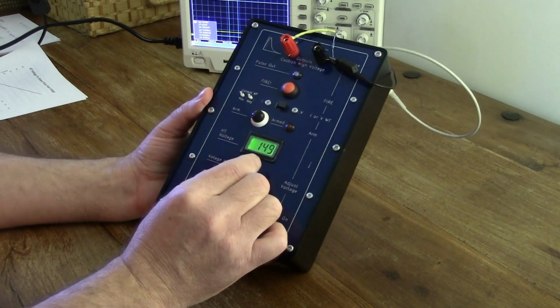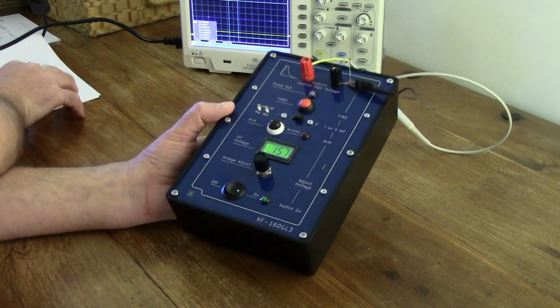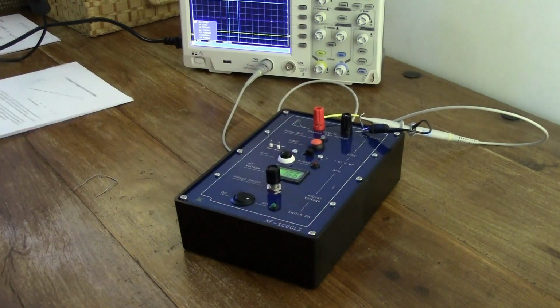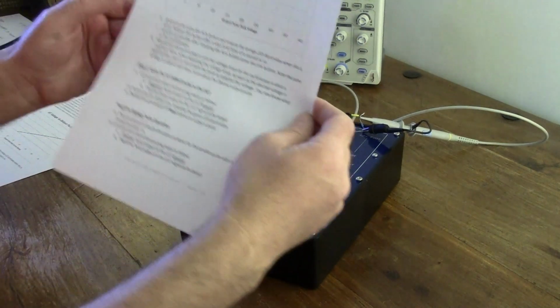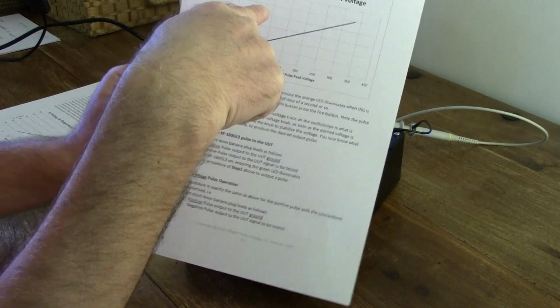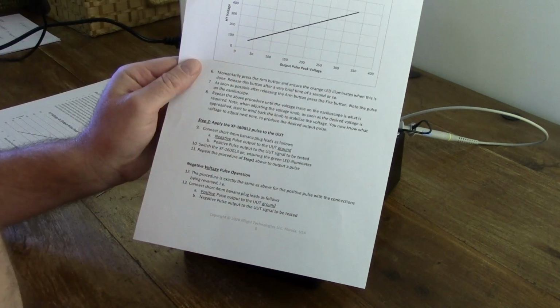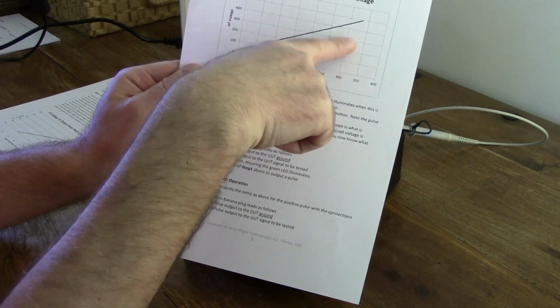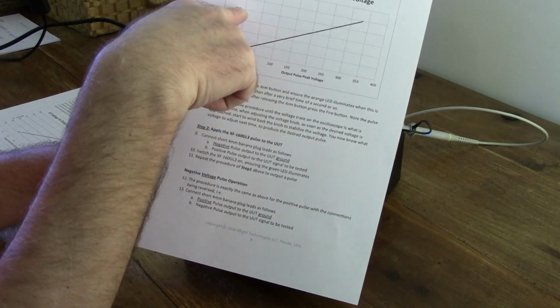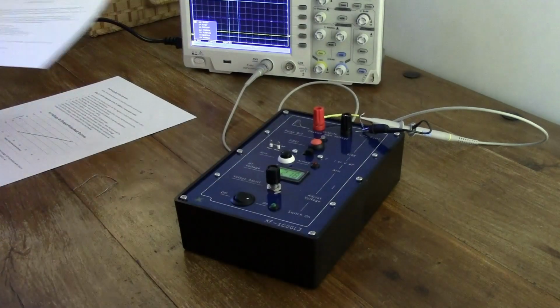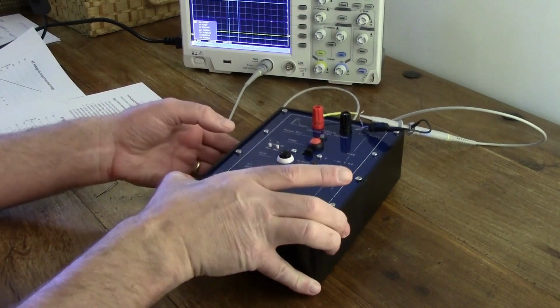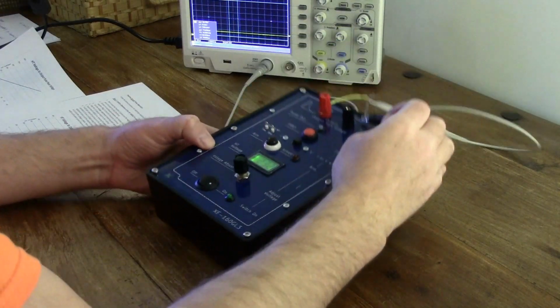And with reference to the user guide, you can see here that if we're looking to generate a 300 volt peak level 3 pulse, then we look that up, and it means we need to adjust the voltage to about 440 volts. So let's do that. Let's connect that wire back on.